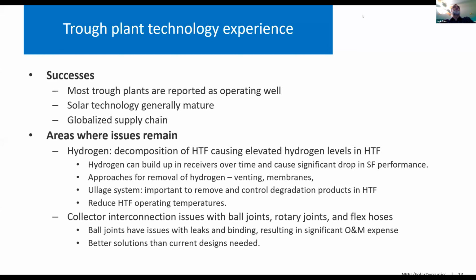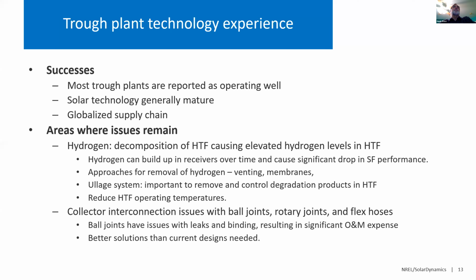There's been a lot of work done in recent years looking at removal of hydrogen from the HTF through venting or membranes in the HTF system. Also, what appears to be very important is that the ullage system for the plant needs to be in service and designed to remove both the high and low boilers. One of the other considerations is that plants ought to consider reducing their operating temperatures. Over the years, operating temperatures keep increasing on new plant designs, trying to tweak out efficiency, but as a result, that causes a faster degradation of the HTF. Through addressing these different issues, we think this is a resolvable problem, but each plant that's operating now has to consider how to address it.